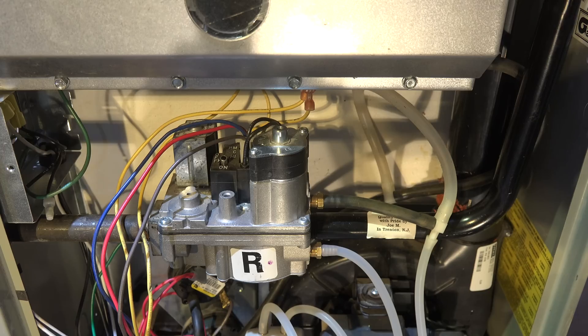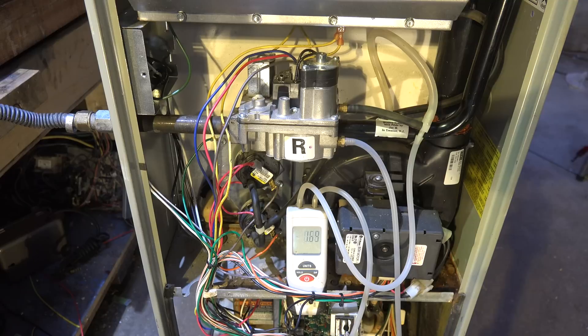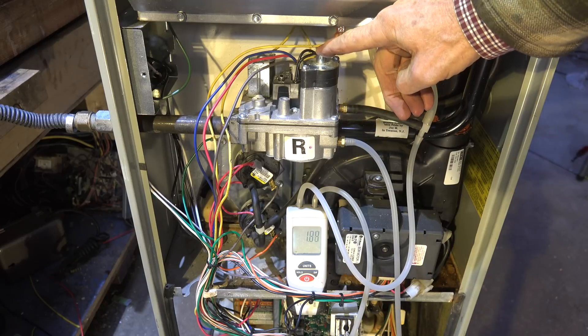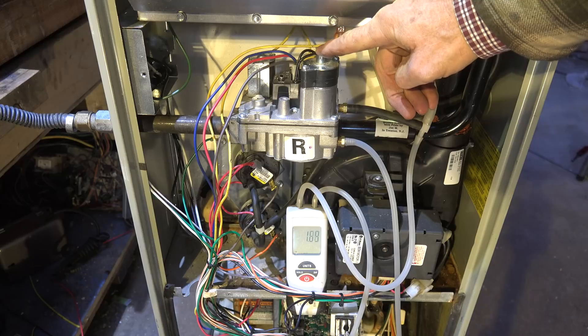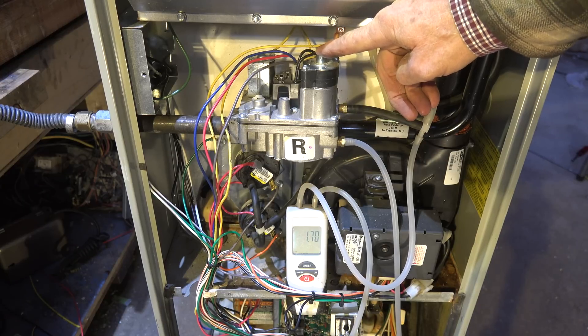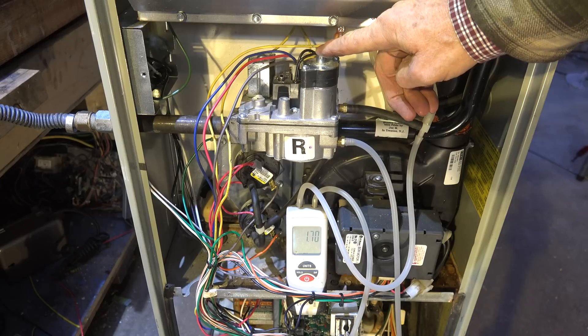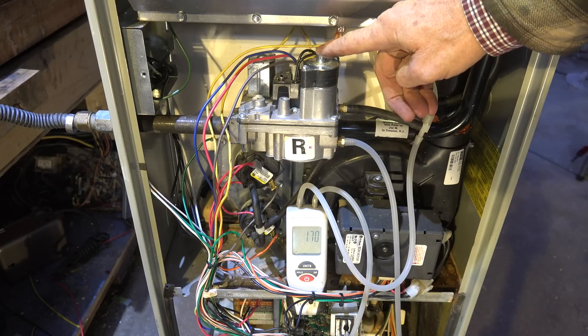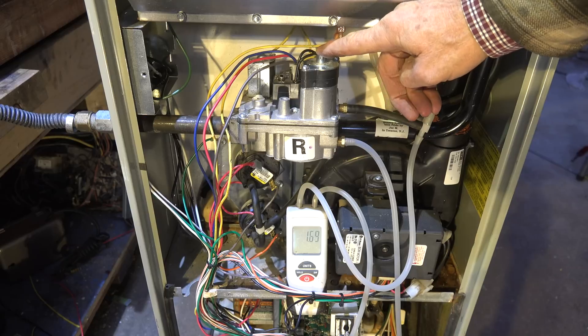We are running now. Notice I'm showing 1.90 — that's too high; 1.7 is as high as it should go. Let's cover this up. That puts us down pretty much to the high end of first stage, and that's okay. Remember you have to cover that opening.